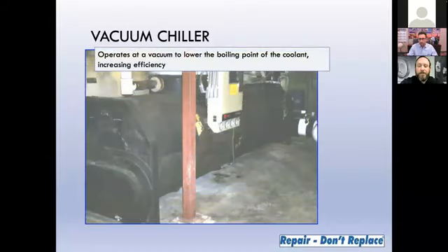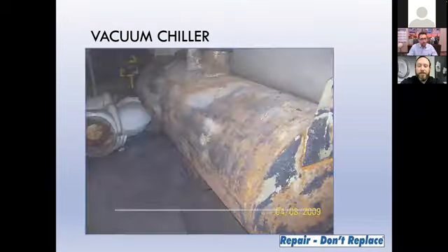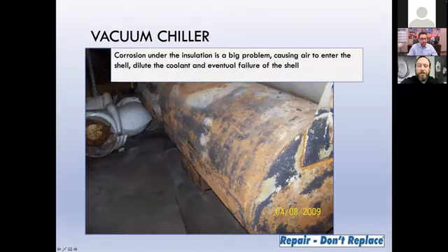Some of the problems that we have been resolving more and more are the results of external corrosion on vacuum chillers. Chillers operate at a lower boiling point for the coolant, which increases the efficiency of the unit. What happens is the insulation, as it ages, starts to allow water or condensation to get under the insulation, causing corrosion issues on the external surfaces. Corrosion under insulation is a big problem for our customers in many instances, and if it's not treated, it can cause air to enter the shell from the corrosion, dilute the coolant, and eventually cause failure of the shell itself.